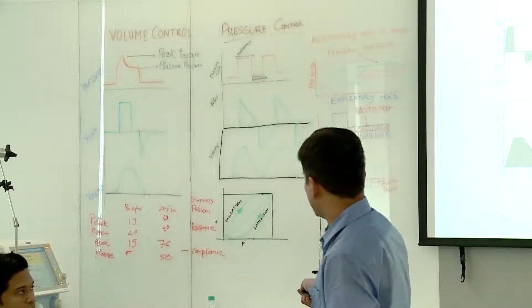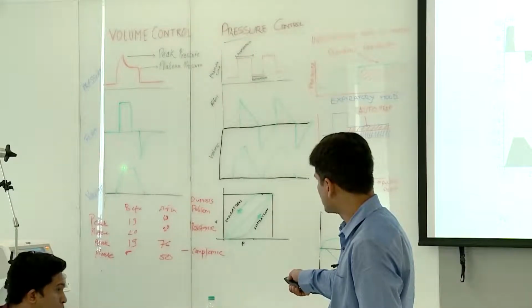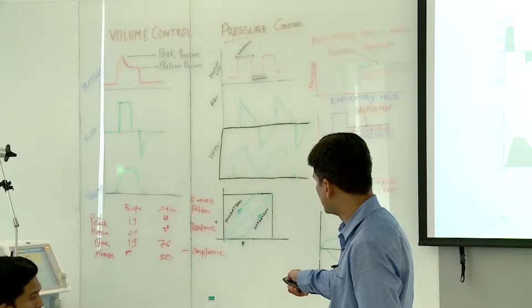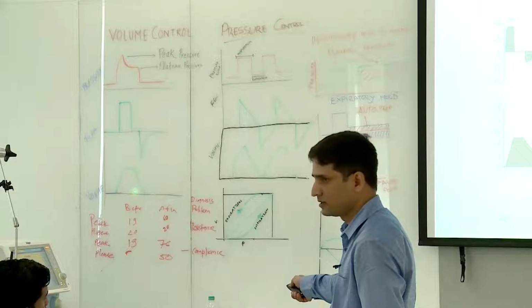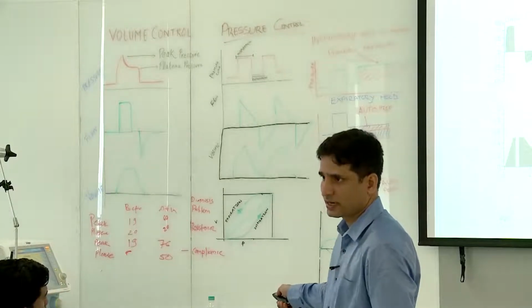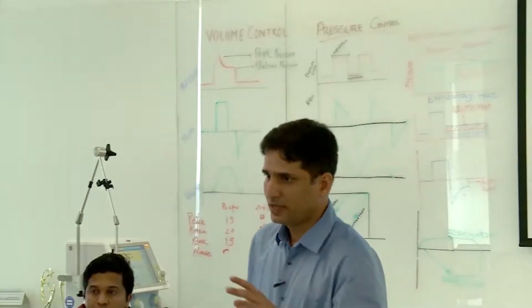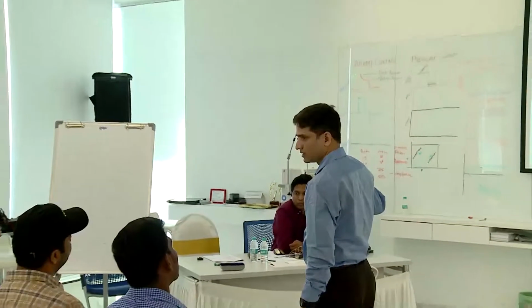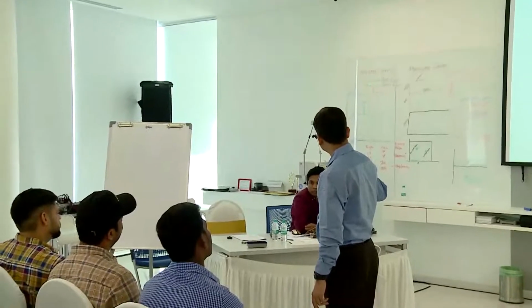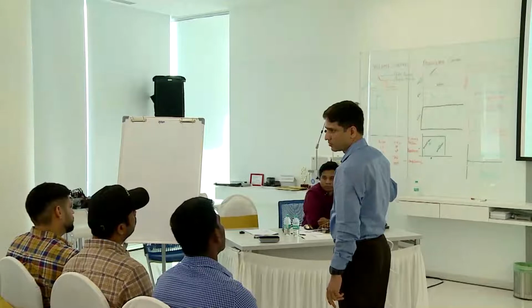And if you see the tidal volume, once the flow or pressure builds up in the system, the tidal volume also builds up, and the volume after that remains constant, and here the expiratory valve opens and the volume again comes back to 0. So this is the characteristic of volume control ventilation. In volume control ventilation, you see three things. In the pressure time graph, you see two types of pressure. One is the peak pressure, which is the pressure in the airways. You can find a pause and a plateau pressure.